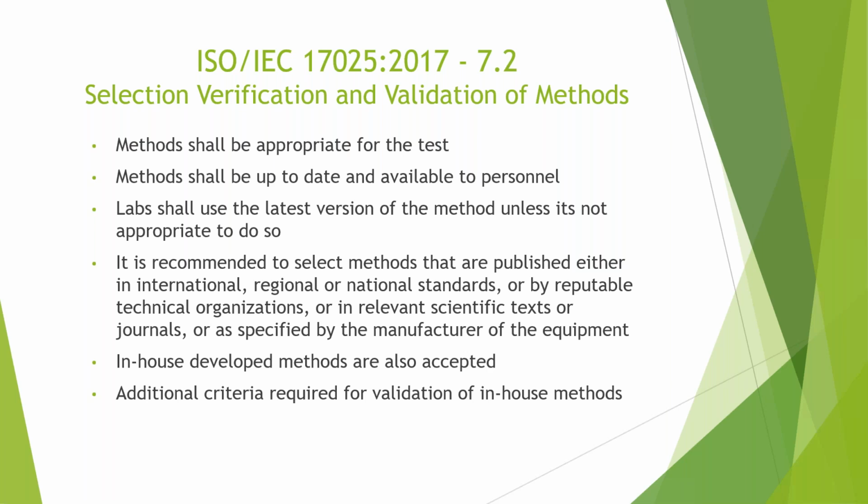But the 17025 standard does state that the methods need to be appropriate for that test. They should be updated and available to all your personnel. And laboratories should use the latest version of the method unless it's not appropriate to do so.